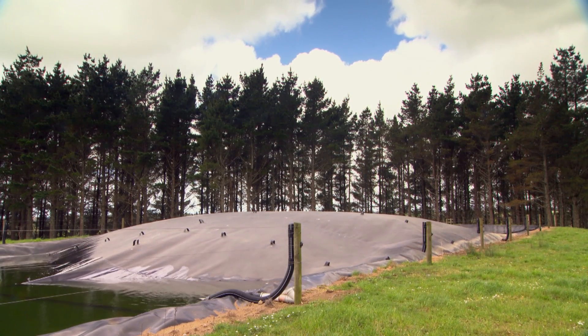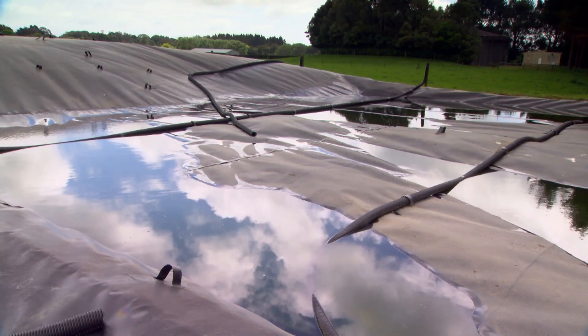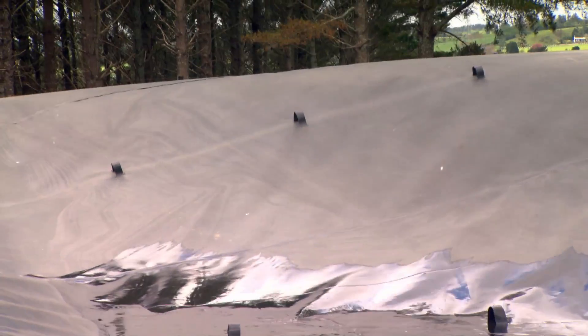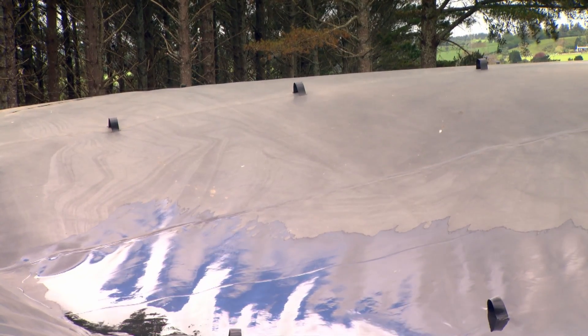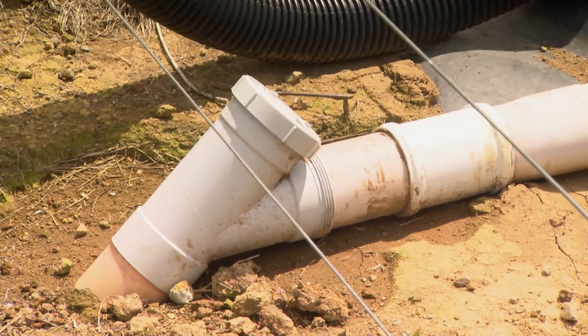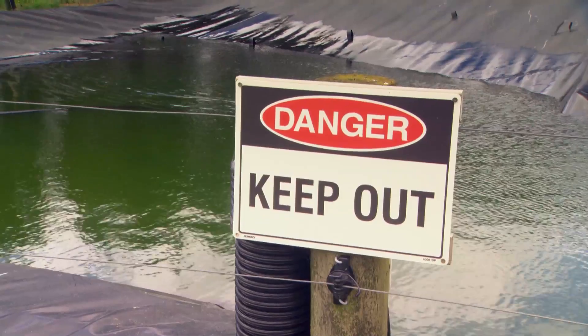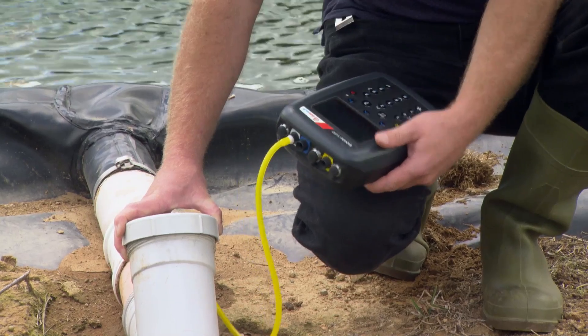The gas naturally bubbles to the top — gas being lighter than water — and accumulates under the cover. Rainwater collects on top and has to be removed so as not to flood the cover too much. Several days of gas production can be stored under the cover. The pressure is not enough to move the gas anywhere on its own, so a small gas blower is used to move it down to the generator. Along the way, several water traps remove water vapour and condensate, and a small filter removes hydrogen sulphide, which is harmful to the generator and motor oil at high concentrations.